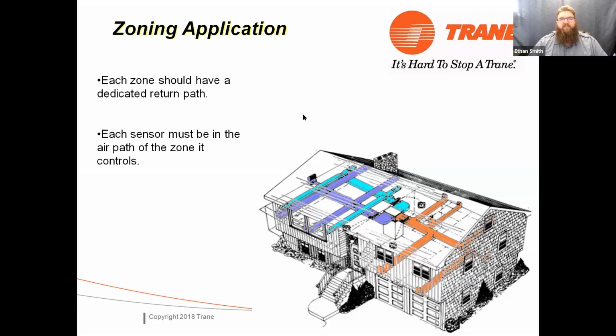Each zone sensor must be in the air path to the zone it controls. You'd think that would go without saying, but I've seen a lot of upstairs, downstairs zones where the thermostat for the upstairs zone is sitting in the hallway that's open to the downstairs zone. Okay, we need to have sensors in appropriate places.